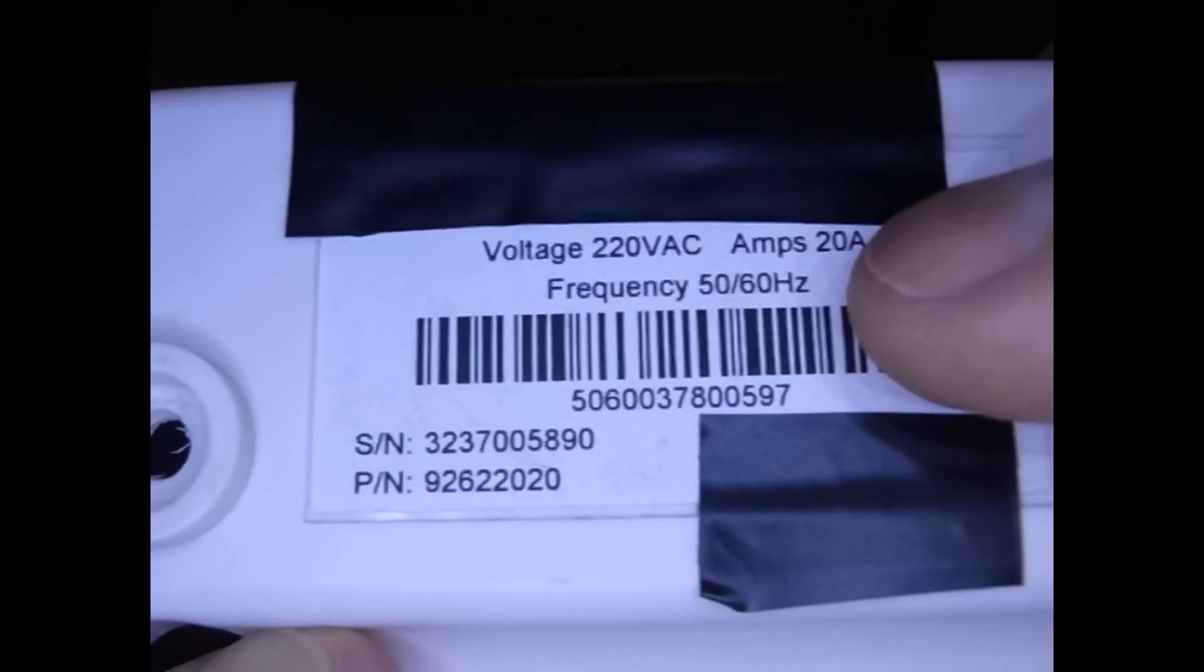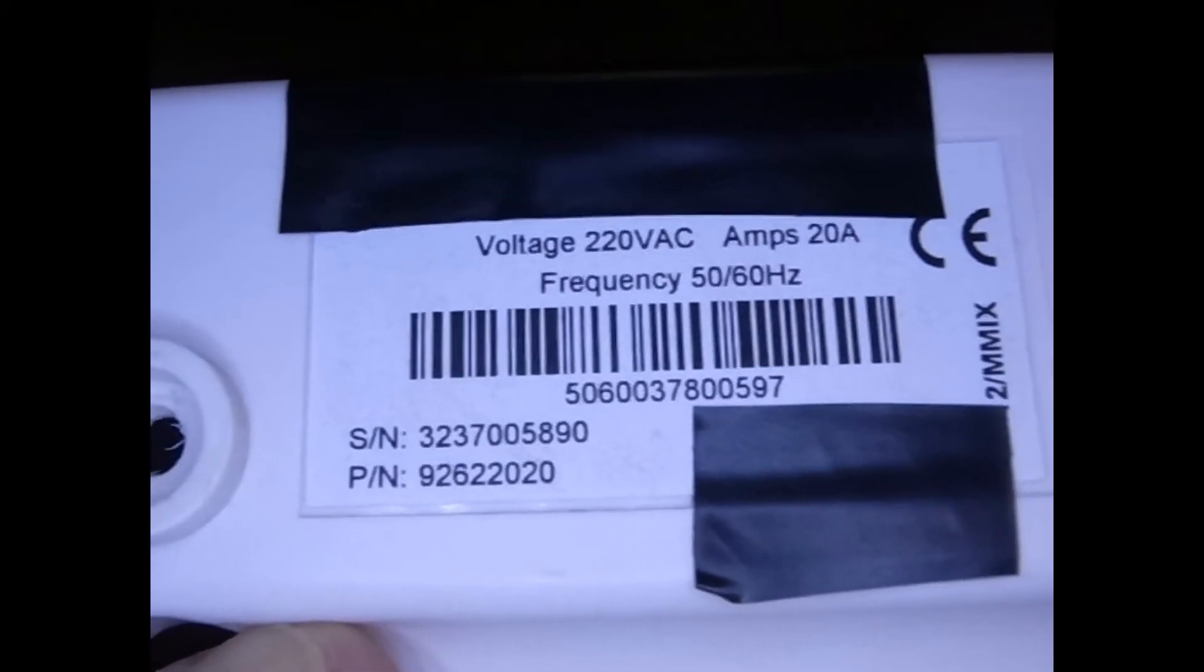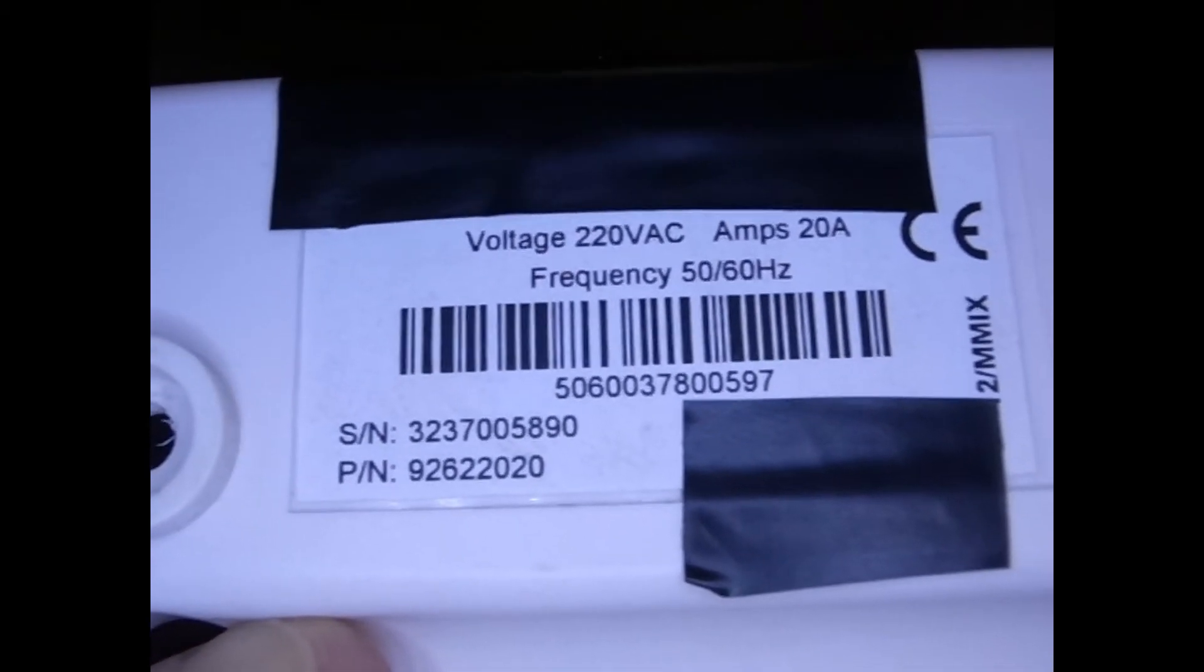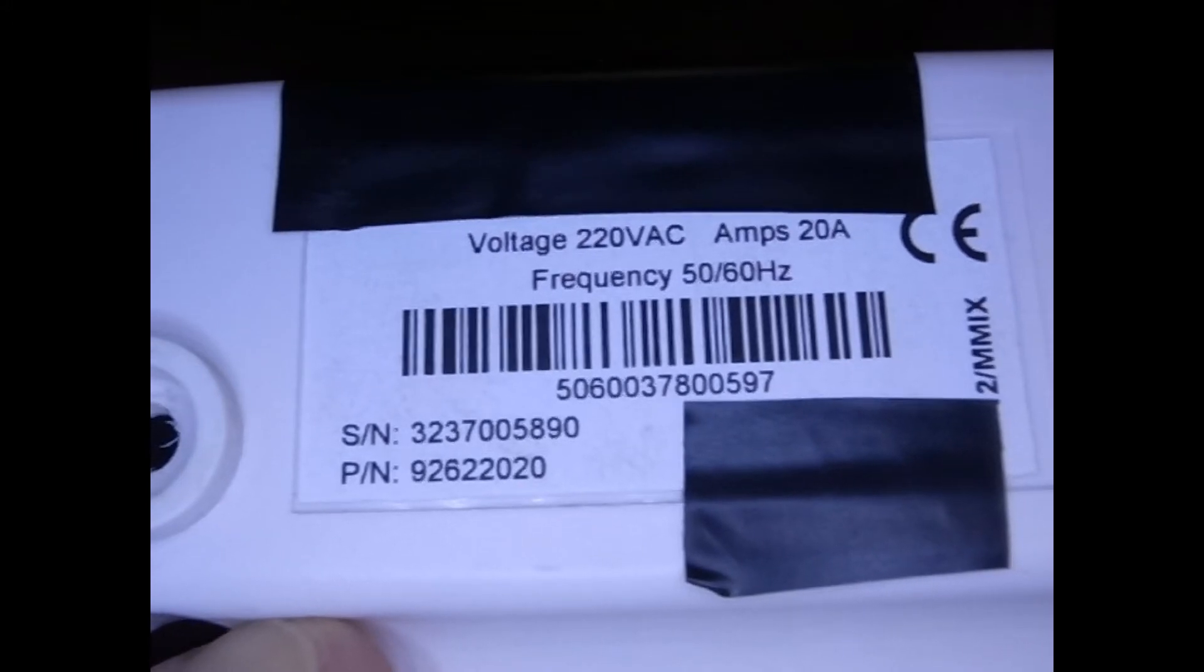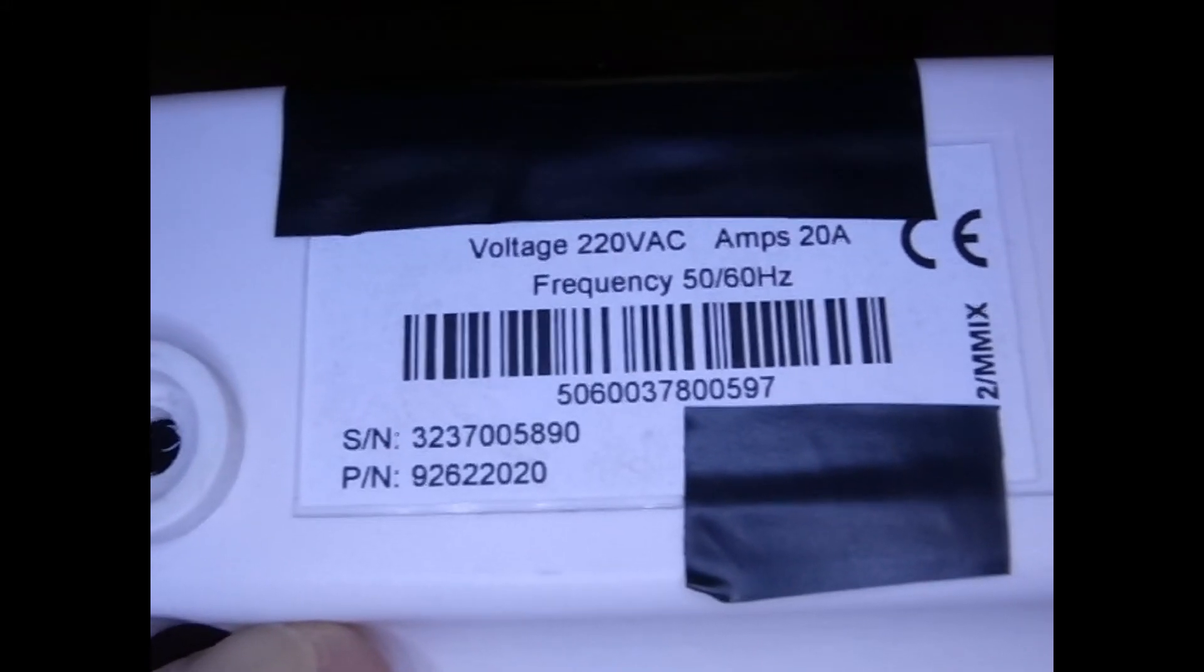As you can see from the label, it's rated at 220 volts, 20 amps frequency, 50 to 60 hertz. It was protecting an air conditioner. It's rated about 7 amps, so this should have had no problems.